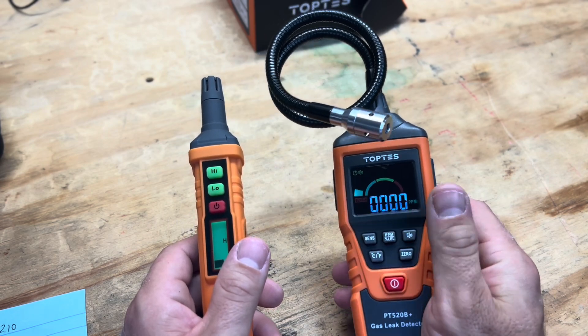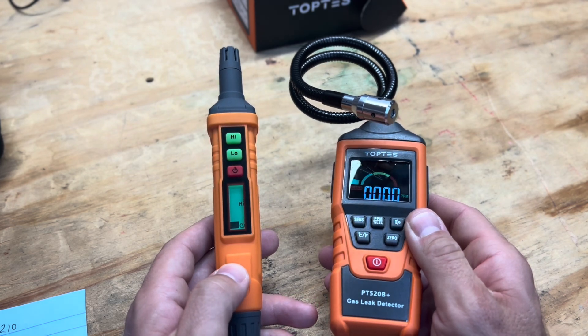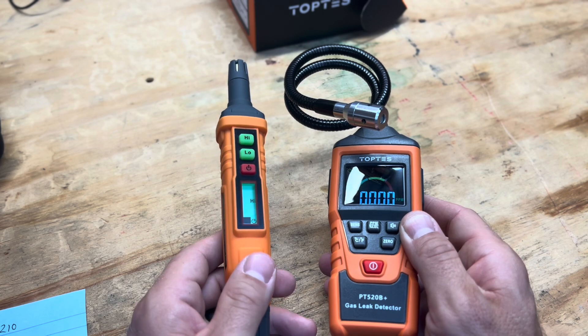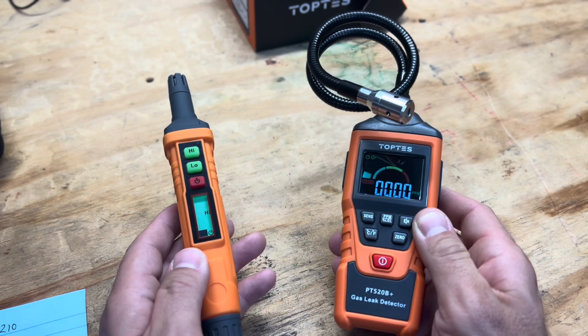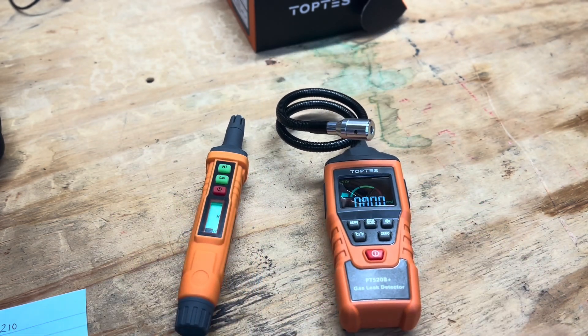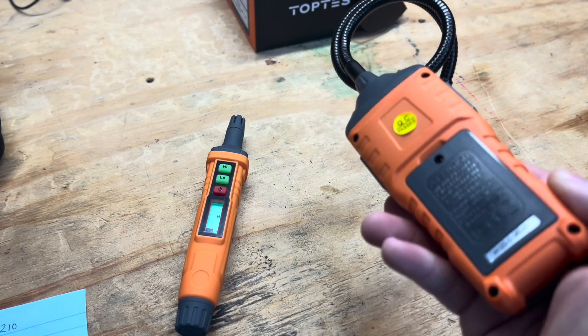Otherwise it's pretty much the same detector. The PT 210 calibrates five seconds slower and picks up gas about a second slower, but both are really good detectors. Hopefully this helps you guys. Thanks for watching, and thanks to Toptes for sending these to me — their affordability is way better than most other combustible gas detectors out there, and their quality is good.